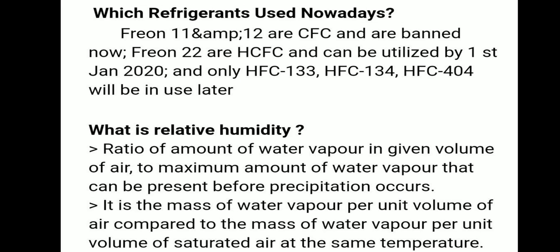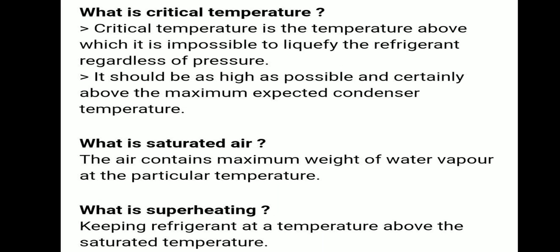Critical temperature is the temperature above which it is impossible to liquefy the refrigerant regardless of pressure. It should be as high as possible and certainly above the maximum expected condenser temperature.